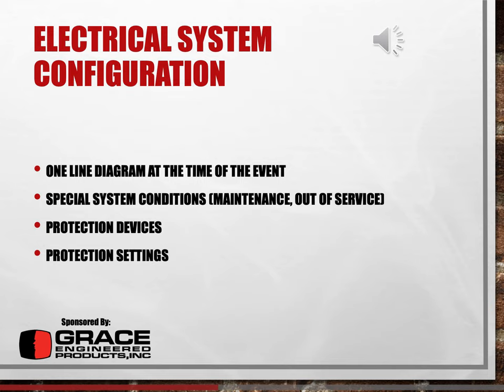You also want to document special system conditions, such as maintenance or certain transformers or generators or equipment that was out of service that may not have had a direct role in the accident, but may have put the system in a condition to permit the accident to happen or to increase the severity or likelihood of an accident. You're also going to want to document the protection devices: what type of relays, circuit breakers, and fuses you have, what their functionality is, and what their settings are. And then you're going to want to download and save any event recordings and oscilloscope waveform captures, and metering and SCADA data, that type of stuff.